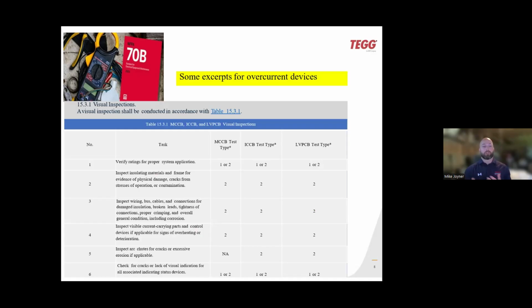So this is some of the visual inspections, the guidelines that we have to go through while we're actually in the switchgear. We are looking at some of the wiring, the cabling; sometimes, throughout the time with the heat and stuff, it can crack. We look for anything that is kind of broken leads. We make sure that all the connections are properly tightened. Look at any kind of visual components. If there are any chutes or cracks, we inspect all the chutes and look for any cracks, any kind of tracking, any kind of corrosion. That absolutely does tend to happen over time.